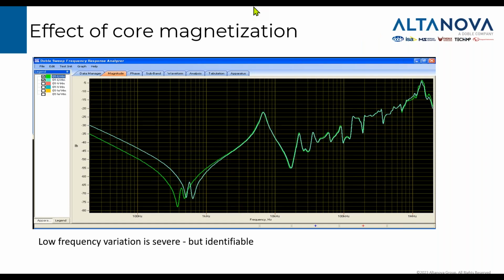The first factor I would like to mention is the effect of core magnetization. If you do the tests during a test schedule, including, for example, winding resistance, you might notice that the trace will be different before and after the winding resistance measurement, because it magnetizes the core. Here we have an example of such a result. We have one trace measured shifted to the lower frequency, another to the higher frequency range, but the difference is focused on the low frequency range. So this is what you can expect if your core is magnetized. It's fortunately easy to identify, and if you have such results, you can investigate further, demagnetize the core, try again, and see what you are really looking at.